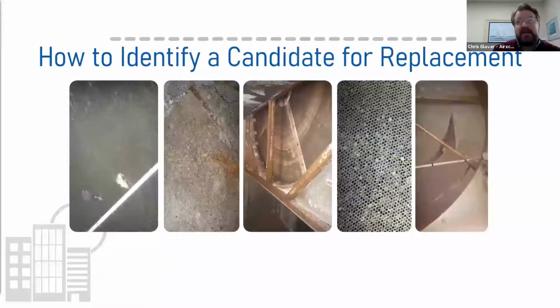Okay, so how do you identify a candidate for replacement? Here are some visual cues of wheels in various states of repair. Each of these pictures demonstrates severe corrosion or plugging or mechanical failure. So it's usually pretty apparent when the device has started to exceed its operational lifetime. As I mentioned before, the typical lifespan that I see for these devices in the market is usually 15 to 20 years. They can exceed that through proper maintenance. I've seen them go well above that. It's just a matter of what condition they are in, what these wheels have been exposed to, and how often they follow the manufacturer's recommended procedure.